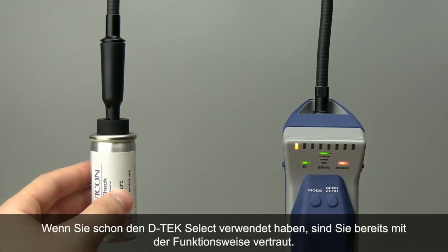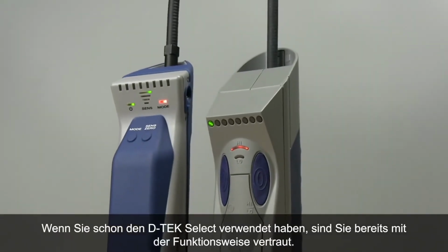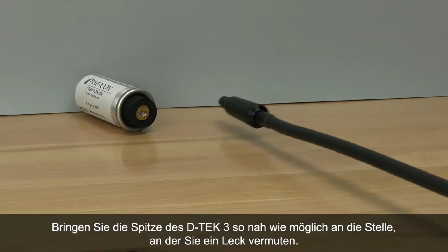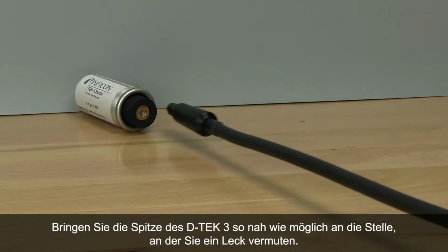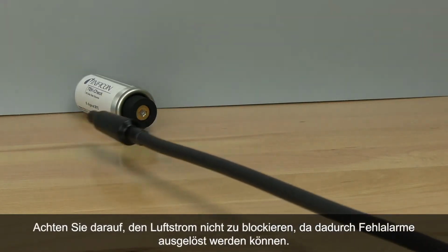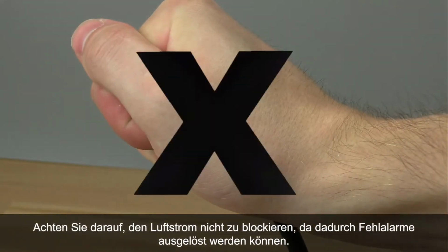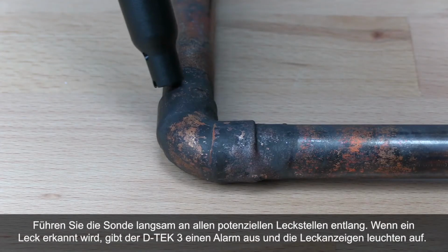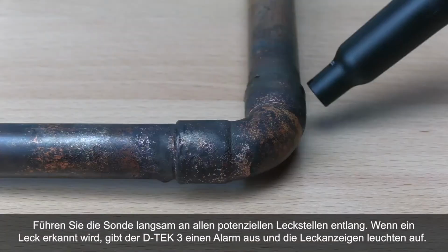If you have used a D-TEK Select, you are already familiar with how this works. Place the tip of D-TEK-3 as close as possible to the suspected leak. Be careful not to block the airflow, as this can cause false alarms. Slowly move the probe past each possible leak point.